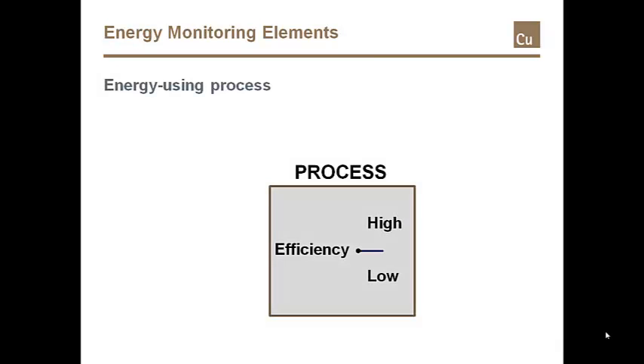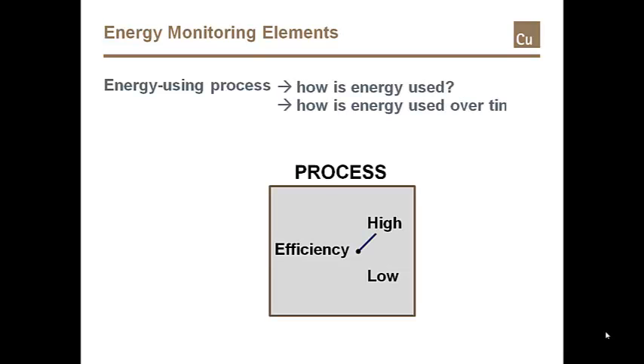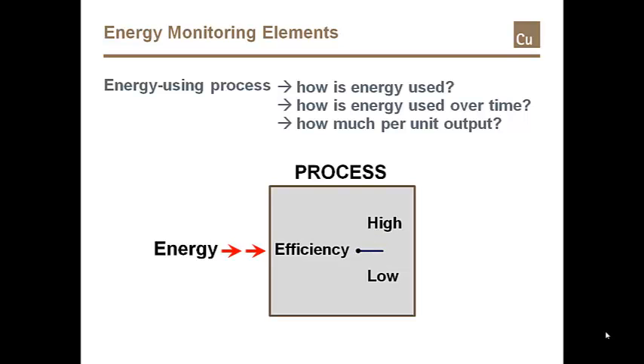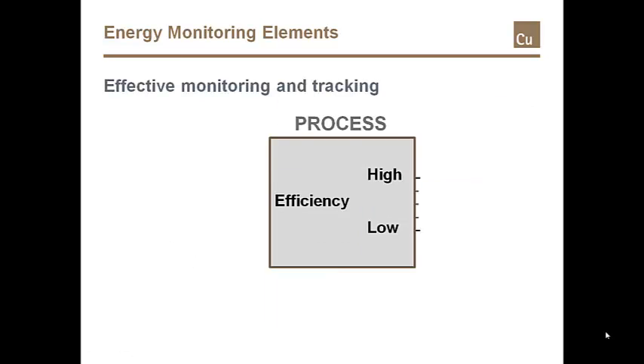Here is a process of some efficiency, whether low or high. What can be known about the energy used? How much over time, or the energy use per unit output? The process may work well and produce. It may be profitable. However, without metering, the energy used by the process cannot be determined or verified. The efficiency is unknown.